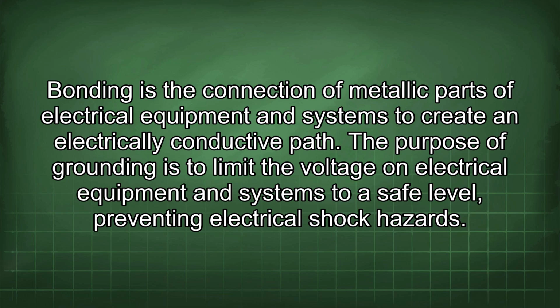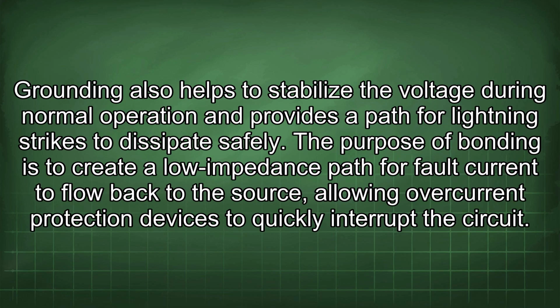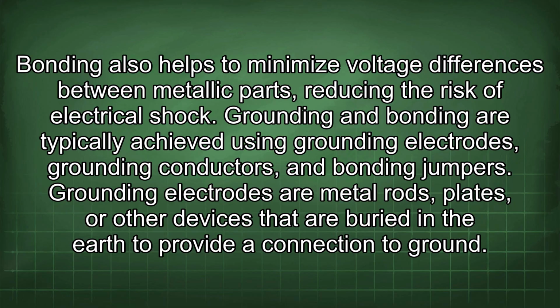The purpose of grounding is to limit the voltage on electrical equipment and systems to a safe level, preventing electrical shock hazards. Grounding also helps to stabilize the voltage during normal operation and provides a path for lightning strikes to dissipate safely. The purpose of bonding is to create a low impedance path for fault current to flow back to the source, allowing overcurrent protection devices to quickly interrupt the circuit. Bonding also helps to minimize voltage differences between metallic parts, reducing the risk of electrical shock.